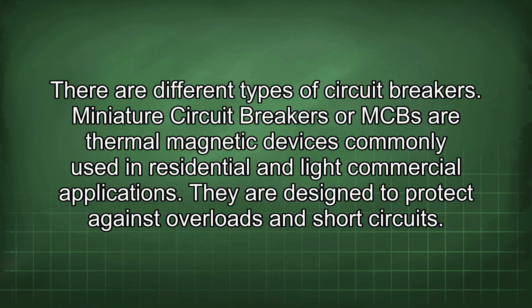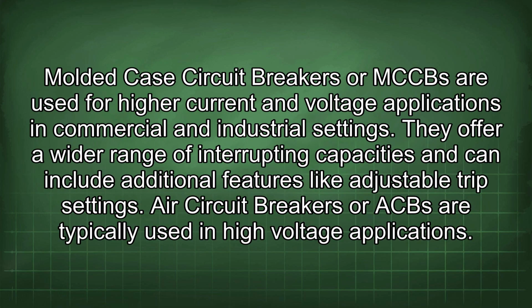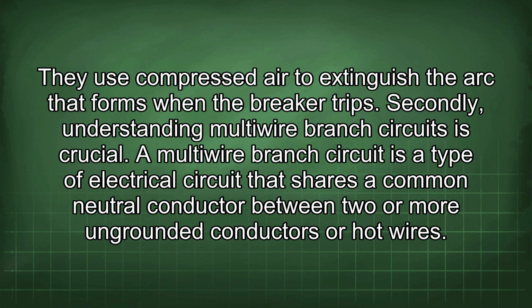There are different types of circuit breakers. Miniature circuit breakers, or MCBs, are thermomagnetic devices commonly used in residential and light commercial applications. They are designed to protect against overloads and short circuits. Molded case circuit breakers, or MCCBs, are used for higher current and voltage applications in commercial and industrial settings. They offer a wider range of interrupting capacities and can include additional features like adjustable trip settings. Air circuit breakers, or ACBs, are typically used in high-voltage applications. They use compressed air to extinguish the arc that forms when the breaker trips.